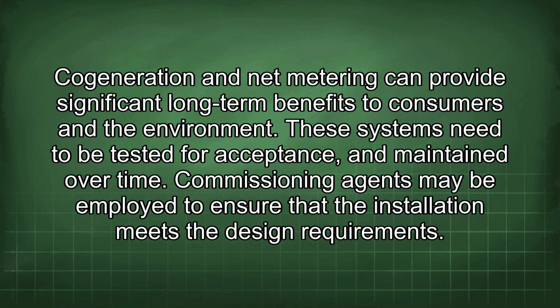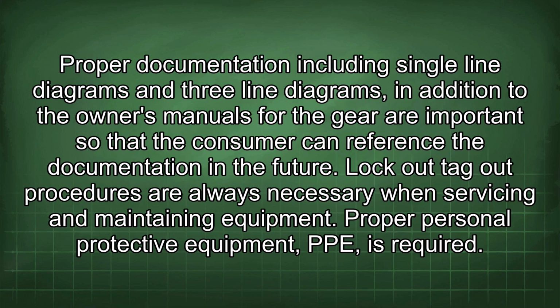These systems need to be tested for acceptance and maintained over time. Commissioning agents may be employed to ensure that the installation meets the design requirements. Proper documentation, including single-line diagrams and three-line diagrams, in addition to the owner's manuals for the gear, is important so that the consumer can reference the documentation in the future.